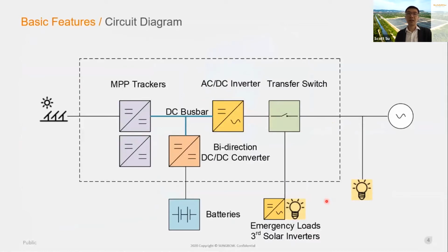Okay, so the fourth section is about our basic features. Here is the circuit diagram. You can see this dotted line box. The interior is the inverter inside. It has 4 main circuits. Here is the maximum power point trackers between the PV arrays and the main DC bus bar. The second one is the bidirectional DC to DC converter between the main DC bus bar and the batteries. The function of that is to control the battery charge and discharge power. The third one is the bidirectional AC to DC inverter circuit. The function is to convert the energy from the DC bus bar, the DC side, to the AC side. It can also absorb the energy from the AC side into the DC side.